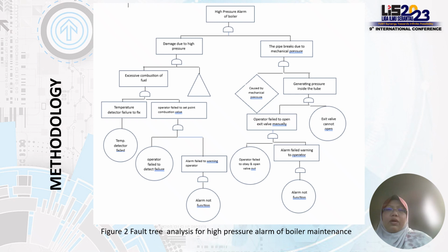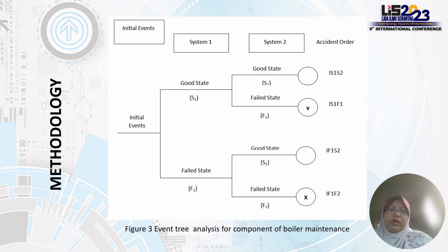For fault tree analysis, here is the methodology I came out with, which is a high pressure alarm of the boiler. And you can see the flow of how the process is. This is the second methodology, for the event tree analysis for the component of the boiler maintenance.